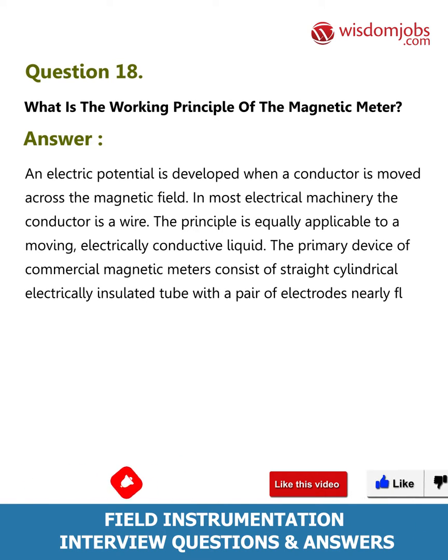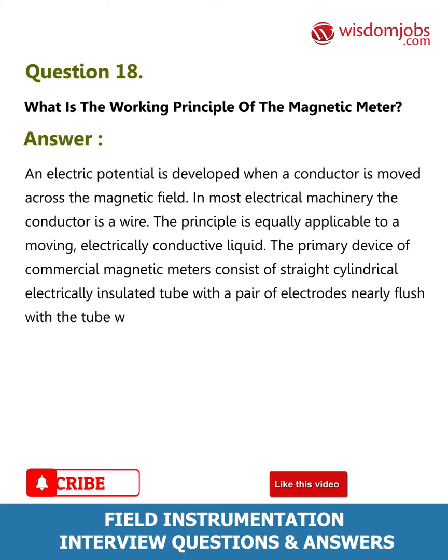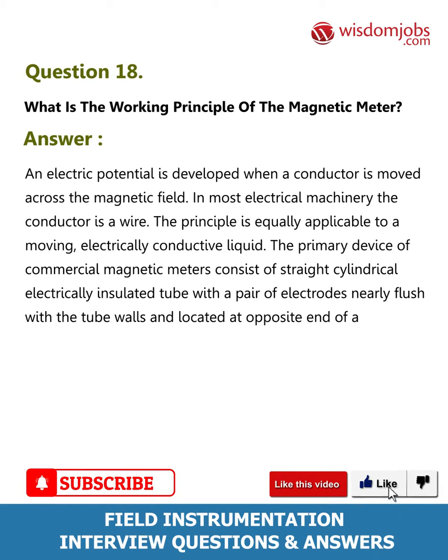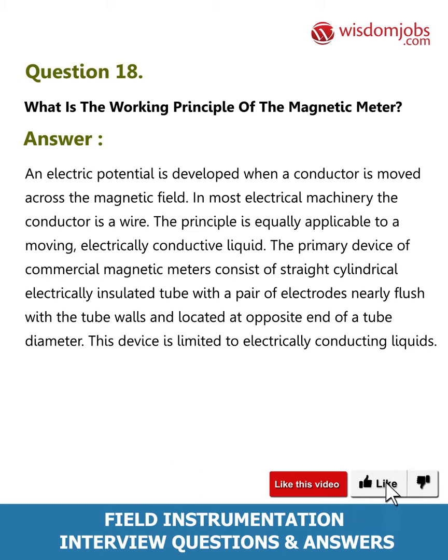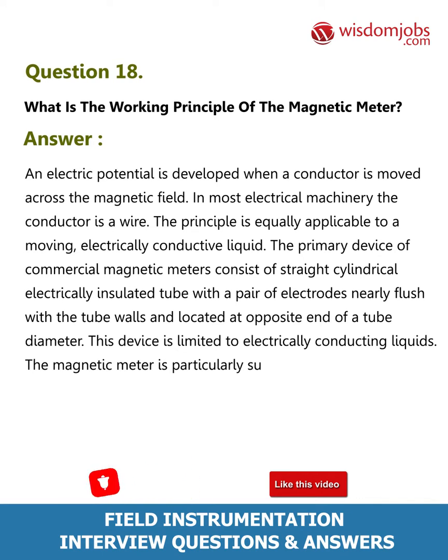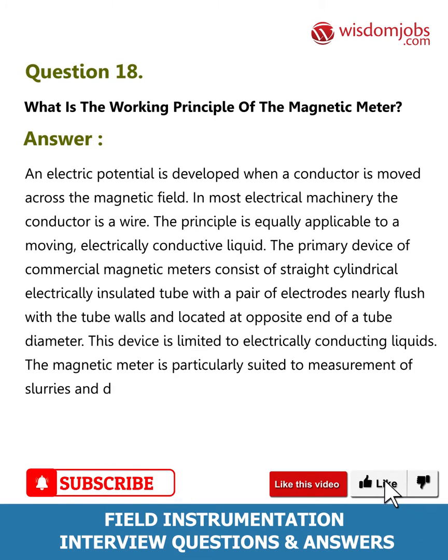The tube has a pair of electrodes nearly flush with the tube walls, located at opposite ends of a tube diameter. This device is limited to electrically conducting liquids. The magnetic meter is particularly suited to measurement of slurries and dirty fluids.